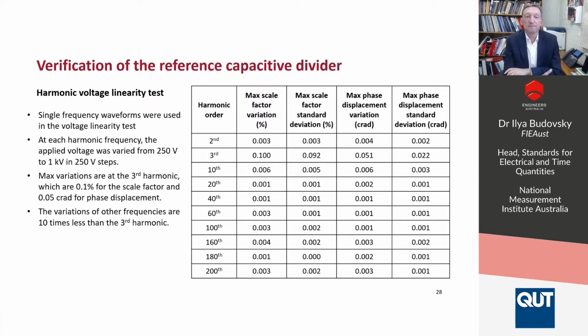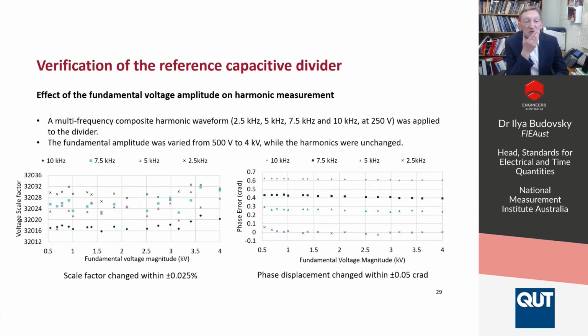We've done a linearity test where we've changed the amplitudes of harmonics, and we're getting very reasonable results for the linearity, both in phase and quadrature, as you can see. And then, most importantly, all the previous tests were at single frequency. What we've done is we've generated composite signals with a number of harmonics between 2.5 and 10 kilohertz, and added up to 3 kilovolts of fundamental to it to see if there's been any changes. And you can see the changes are really minimal, both for in-phase and quadrature component.